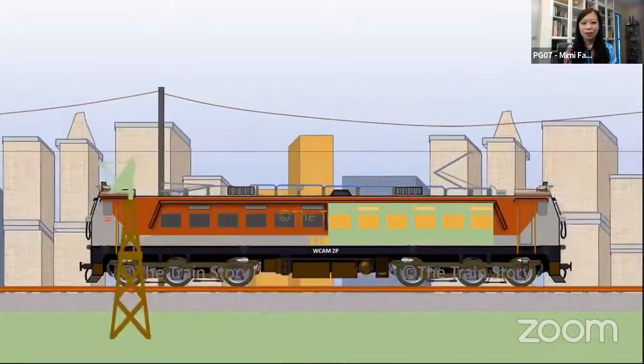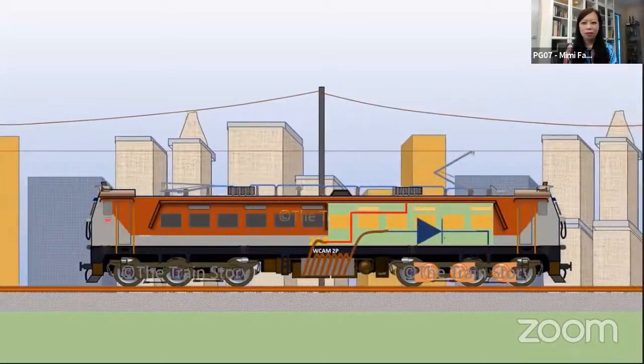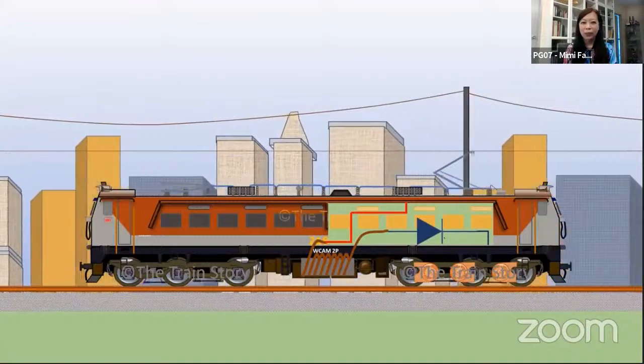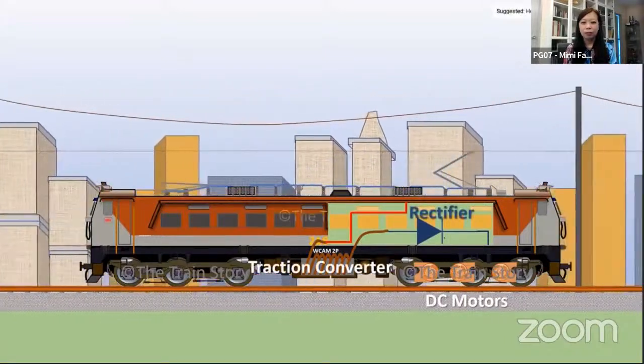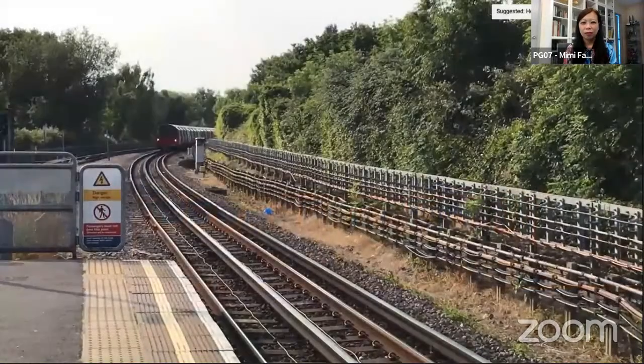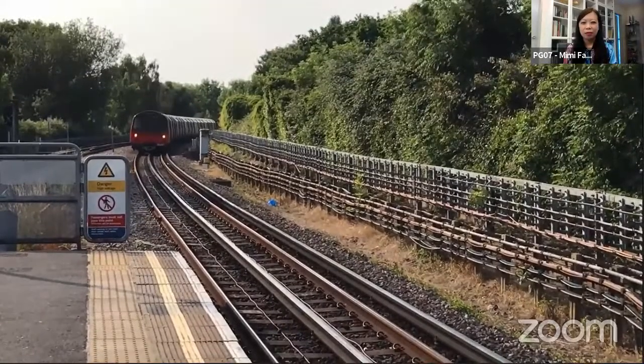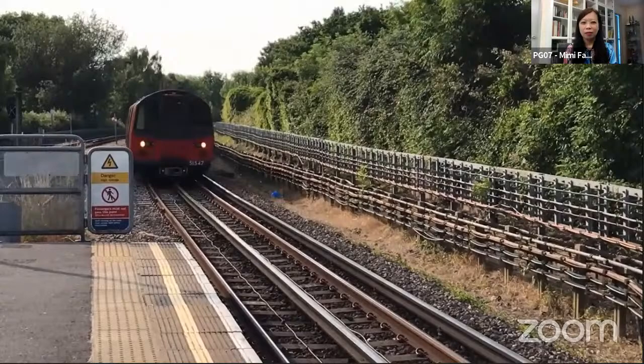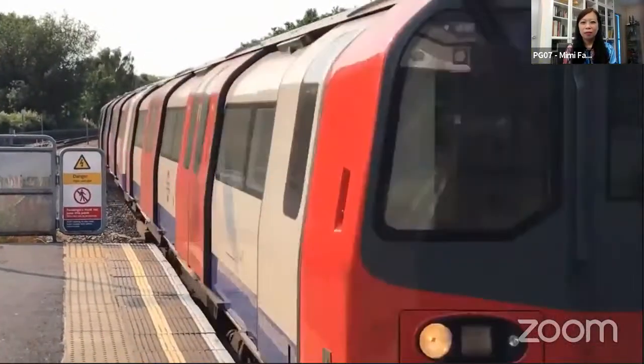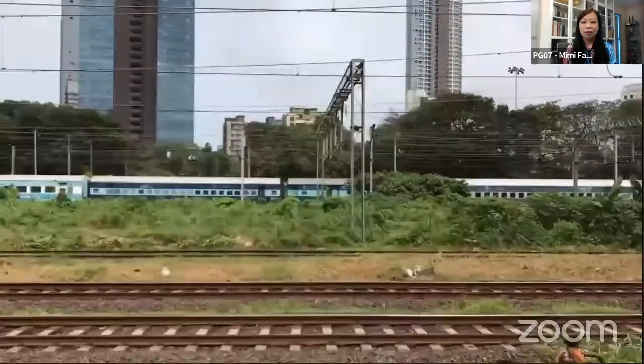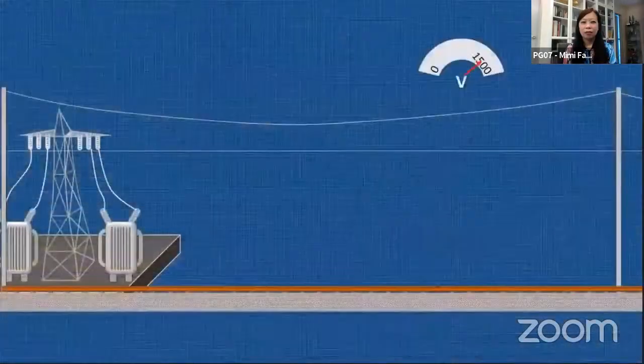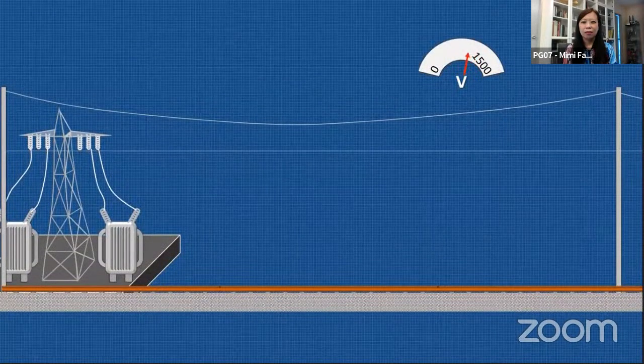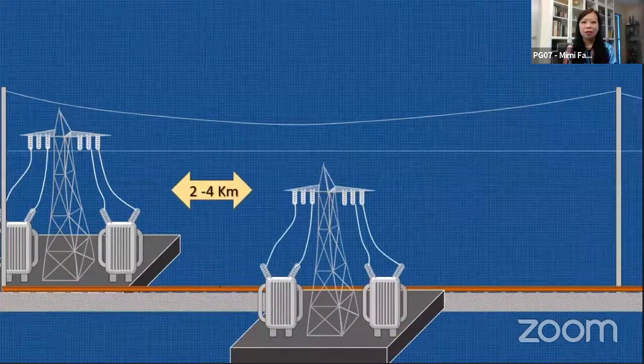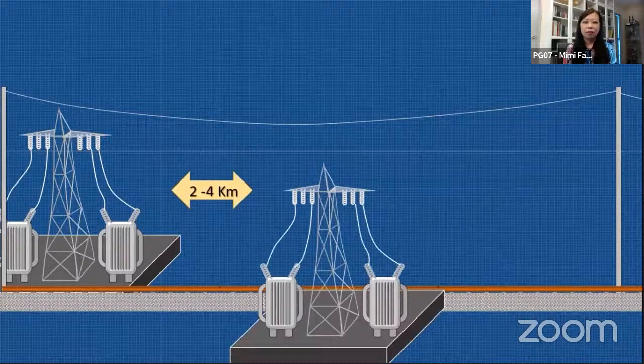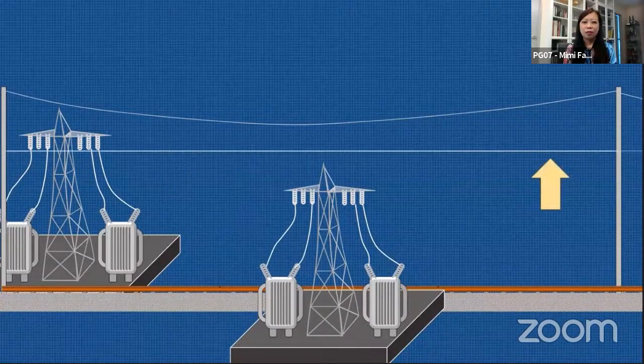Typically, in DC traction systems, three-phase power received from the power grids is de-escalated to low voltage and converted to direct current by the rectifiers and power electronic converters. DC electric power can be supplied to the locomotives through third and fourth rail systems when operating voltages are between 600 to 1200 volts. For higher voltages of 1500 to 3000 volts, electric supply is provided by the overhead catenaries. However, DC voltage decreases with increasing length, necessitating expensive substations at frequent intervals, typically between 2 to 4 kilometers. The overhead wire or third rail must be relatively large and heavy.